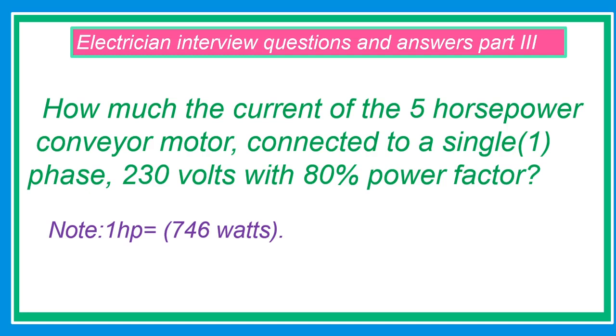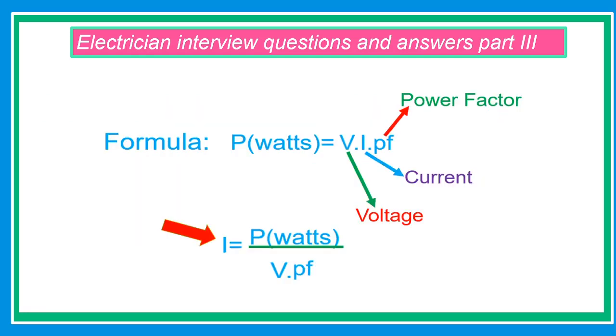How much is the current of a 5 horsepower conveyor motor connected to single phase 230 volts with 80% power factor? Note: 1 horsepower equals 746 watts. This is the power formula with respect to motors: P equals V times I times power factor, where V is for voltage, I is for current, and PF is for power factor. And if we are going to find the formula of current: I equals P over V times power factor.